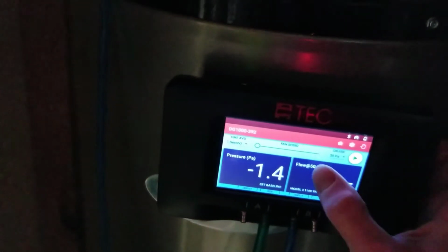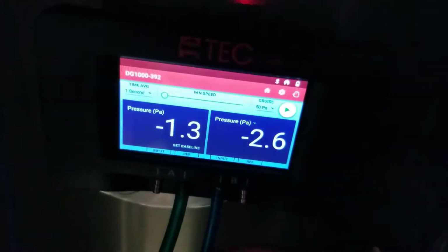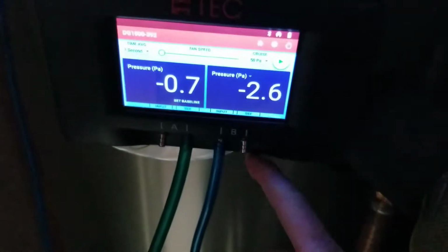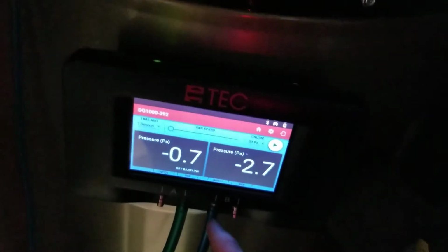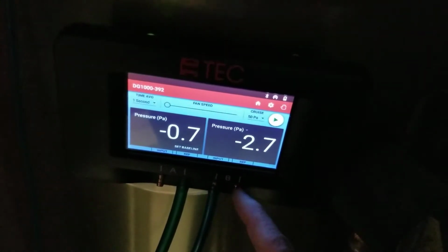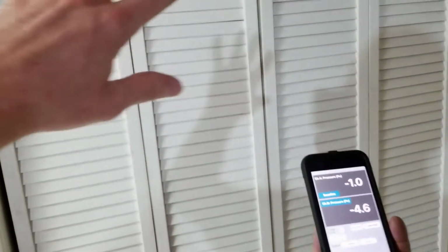Now over on the right hand side, in a few minutes, we're going to be measuring the pressure of the draft on the water heater, or whatever the pressure is inside the vent. We've got our hose going up into the vent right here, and then the reference tap is open, so we are measuring the vent pressure with reference to the CAZ on channel B. Okay, so because our CAZ has these louvered doors, we want to close them as well.